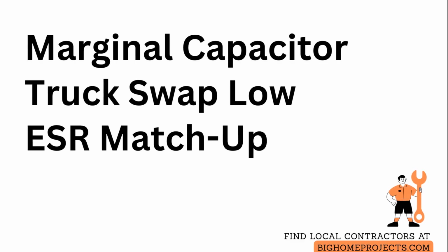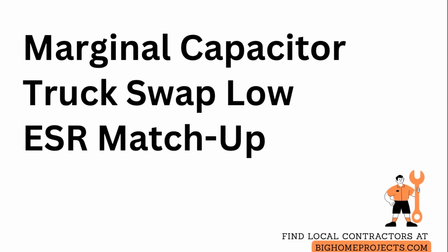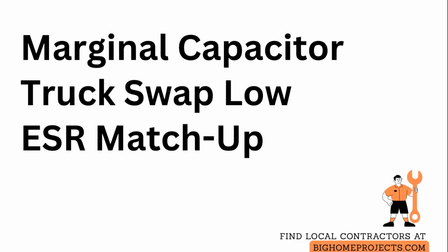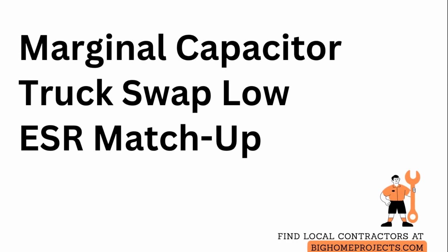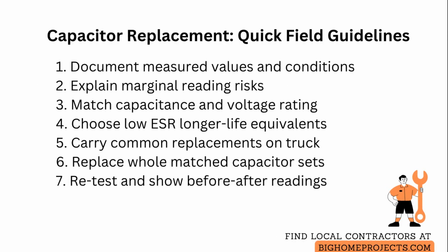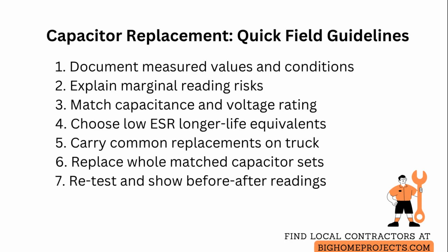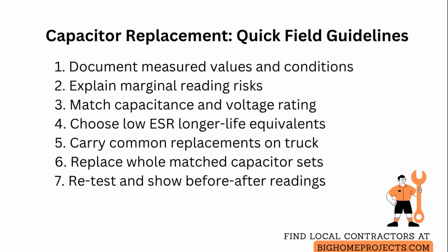If a capacitor tests marginally within specification but shows age-related wear or physical damage, replace it preemptively to avoid imminent failure. When evaluating a marginal capacitor, first document the measured values and the test conditions, including temperature and applied test voltage, so you can justify the recommendation.